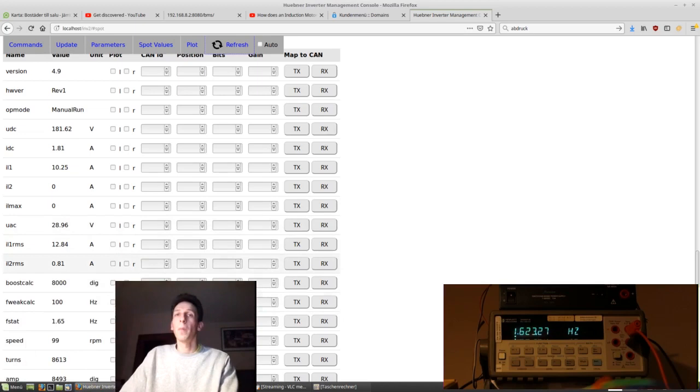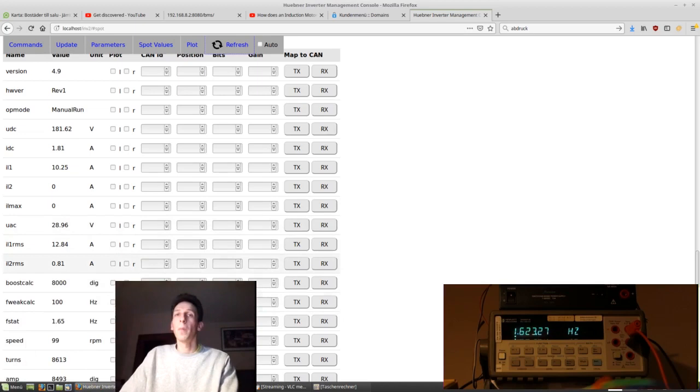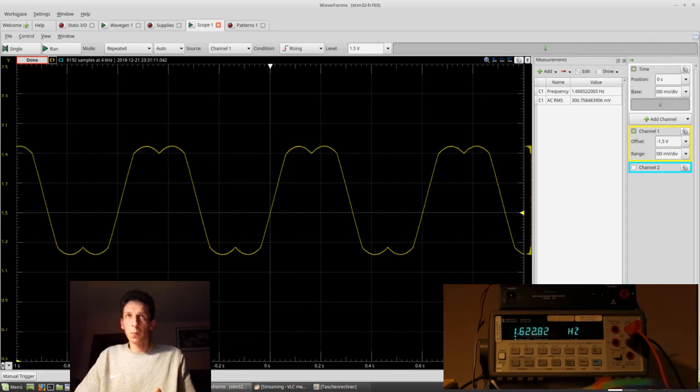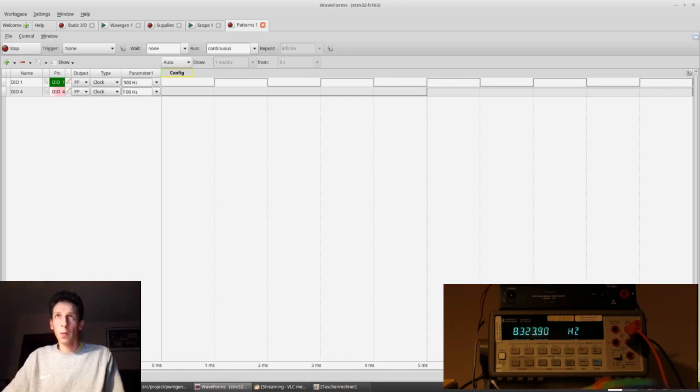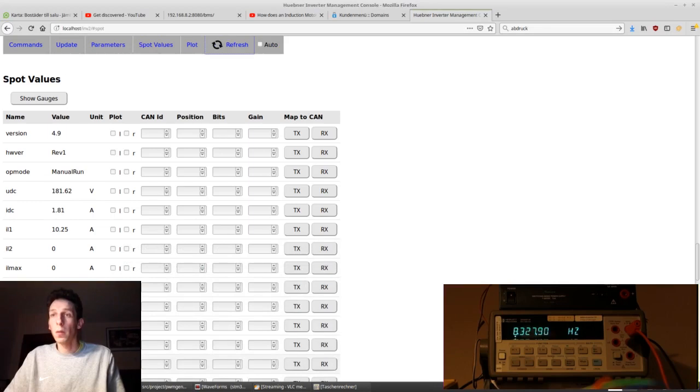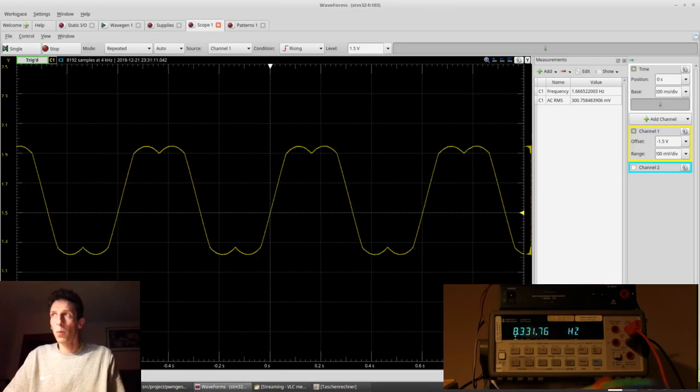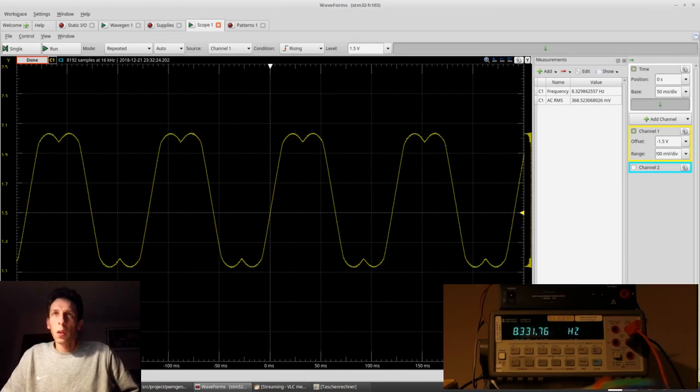And we're getting close to 1.6 hertz. It can't decide. Let's take a look at what the scope thinks of it. Yeah, it doesn't pick up low frequencies like that. I have to change the time base to some really ridiculously high value. Well, not too bad. So, the scope has a better grasp of it. 1.6 hertz, like predicted. And likewise, we should see 1.6 hertz on the inverter display.